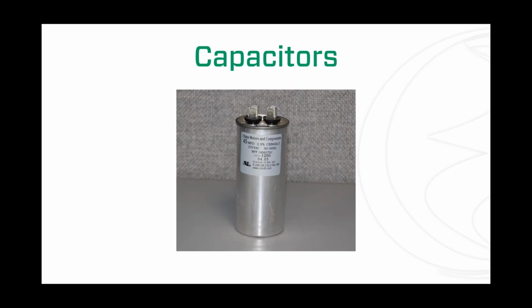Another important fact about capacitors: they have a service life and they will go bad. Capacitors hate starting and stopping. So if you have a pump with capacitors, it's extra important to have good pump run time by setting your float switches properly.